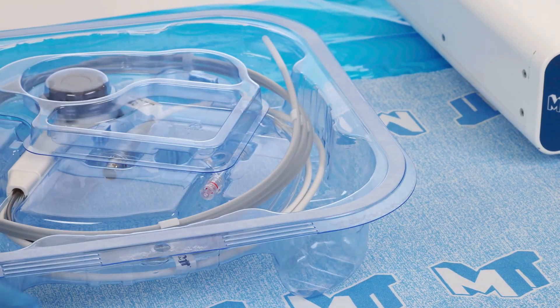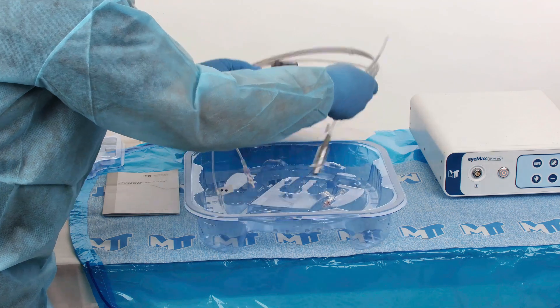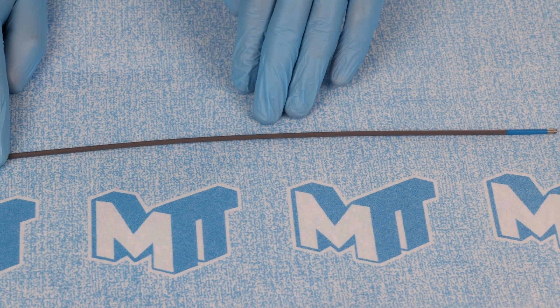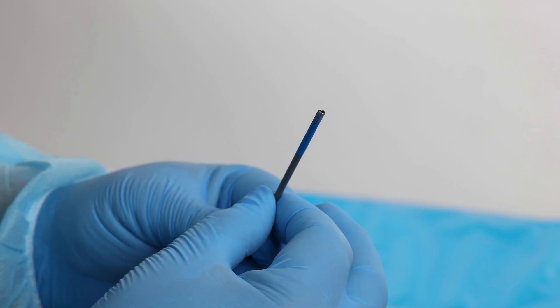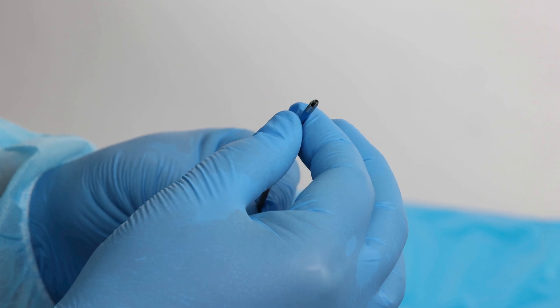Remove the eyeMax scope from the sterile package and check for any damage. Visually inspect the entire surface of the insertion portion. Then visually inspect the distal tip of the insertion portion of the scope for damage, including dents, prominences, cracks, or holes.